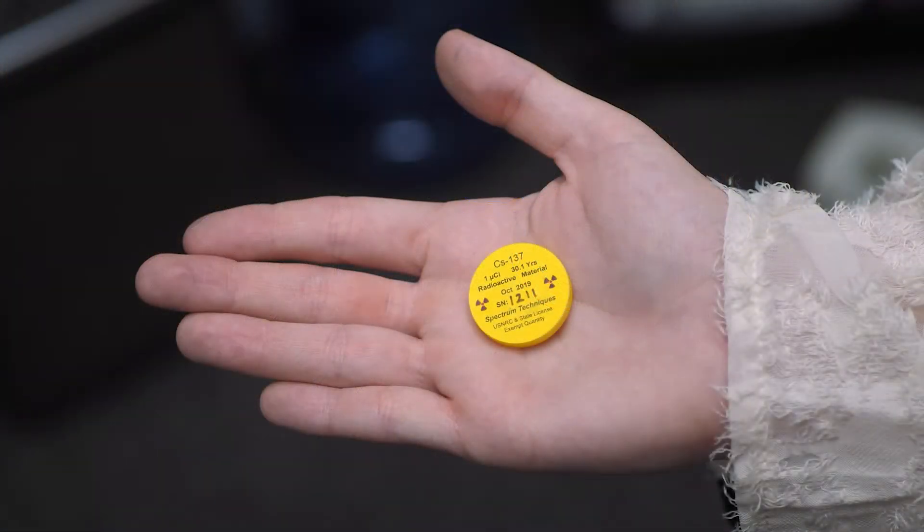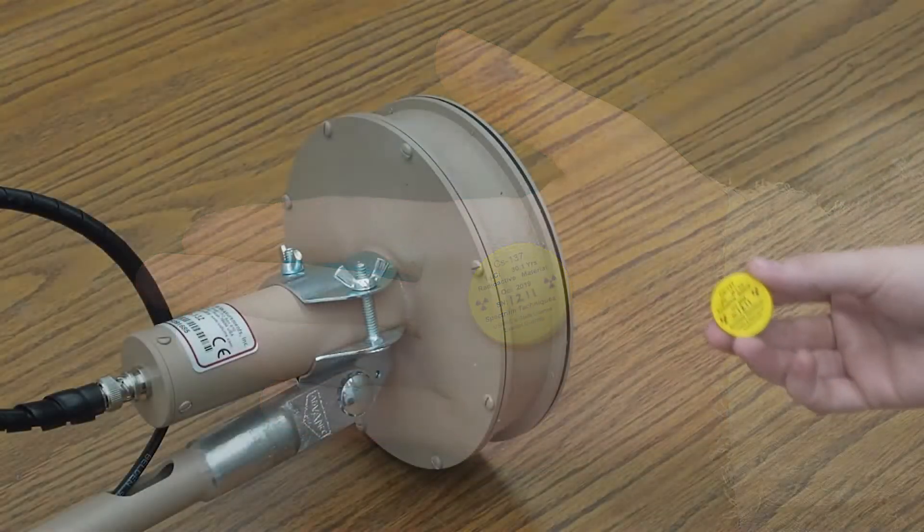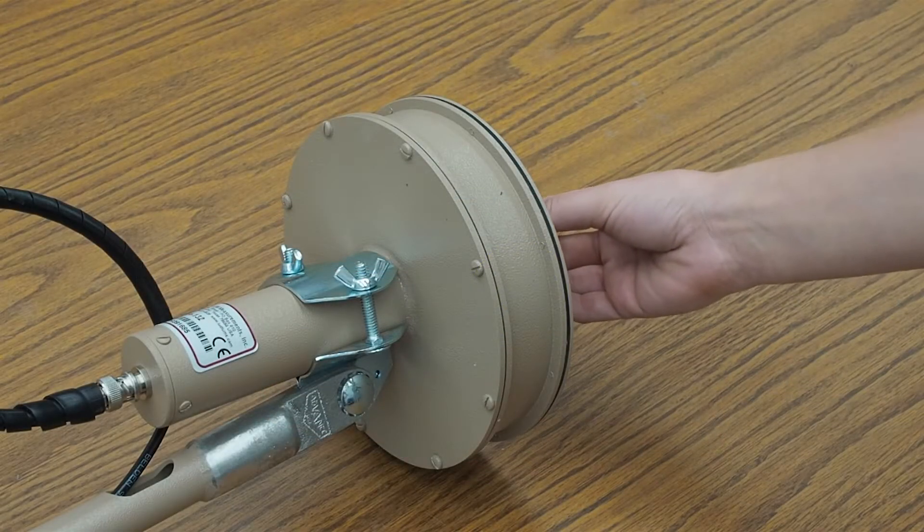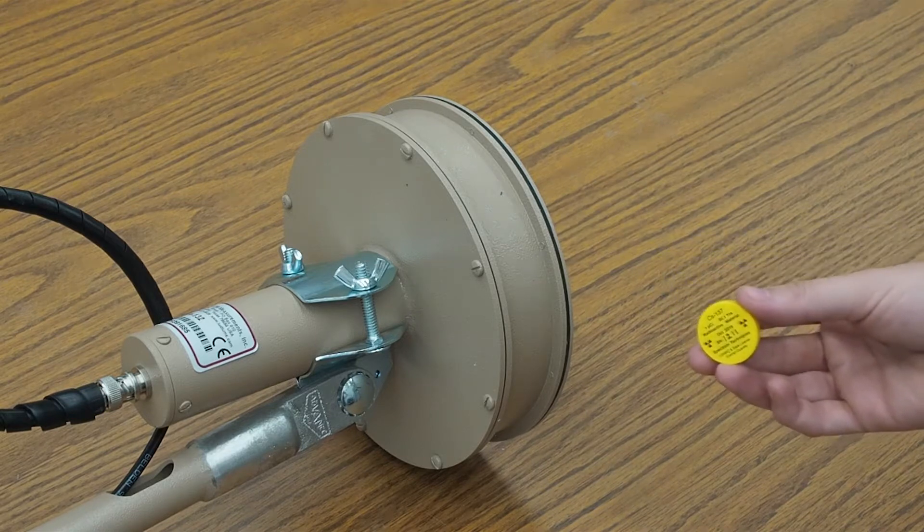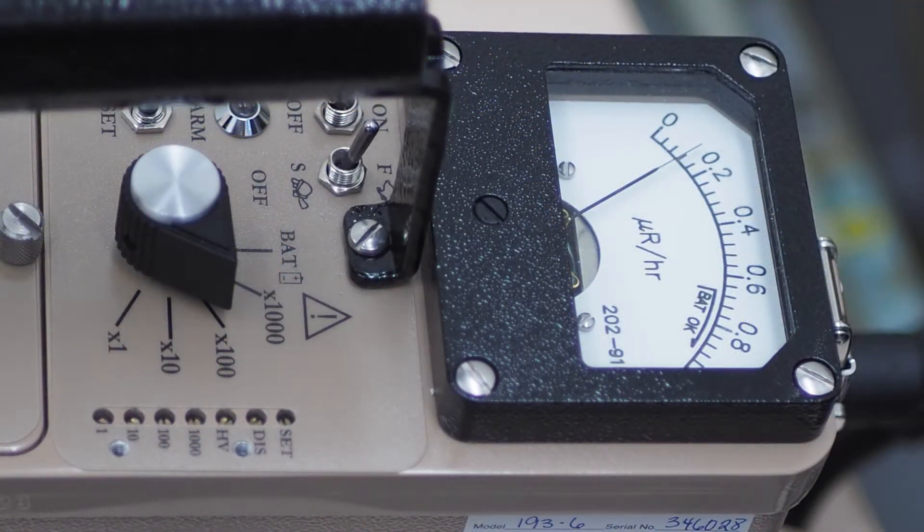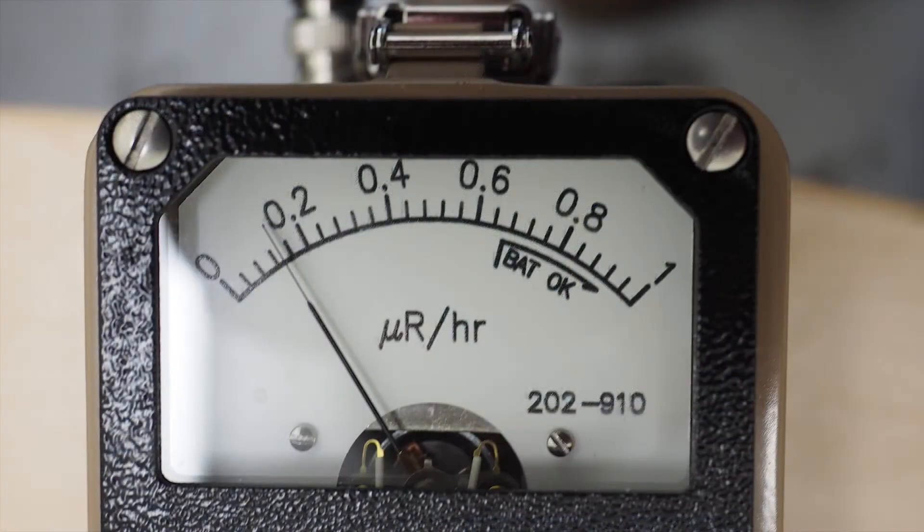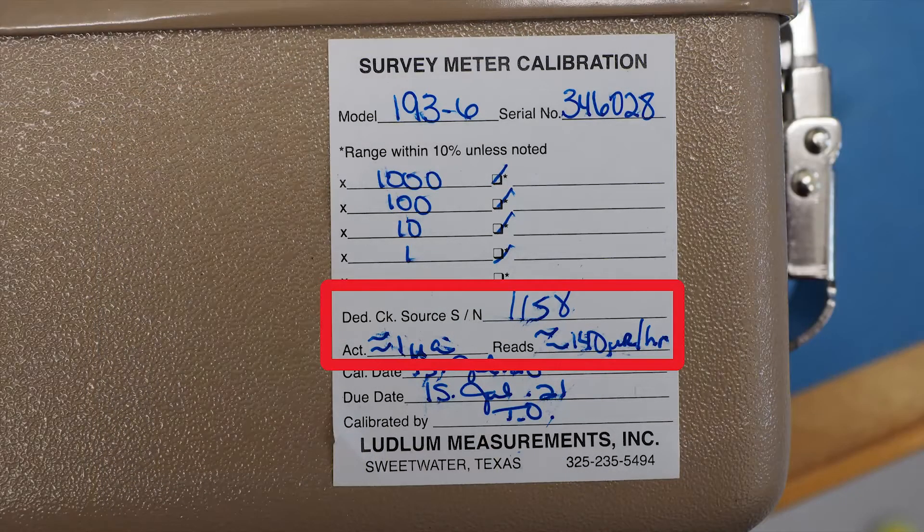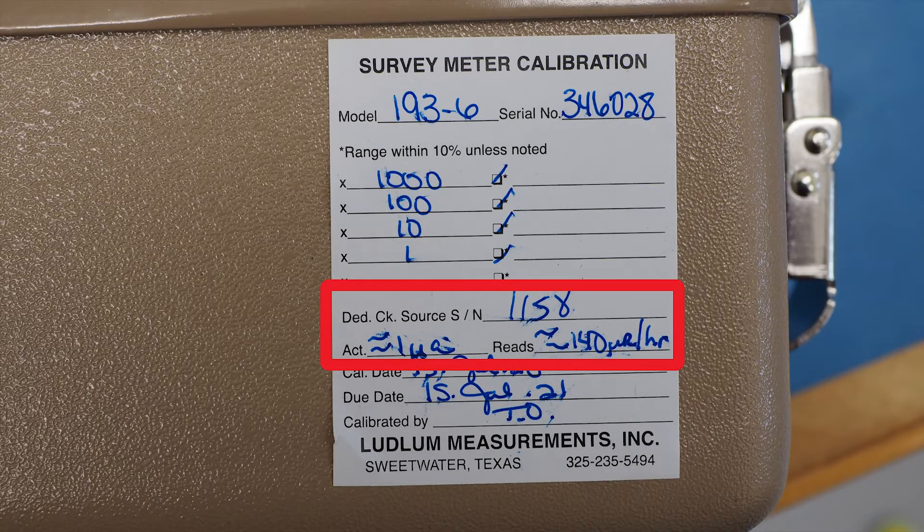If you have a check source, take a reading to see if the instrument reads correctly. Place the source next to the detector and make sure it reads within 20% of the recorded reading. In this example, the meter is indicating approximately 140 µR per hour. The reference check source reading can be found on the Ludlum calibration sticker on the side of the instrument.